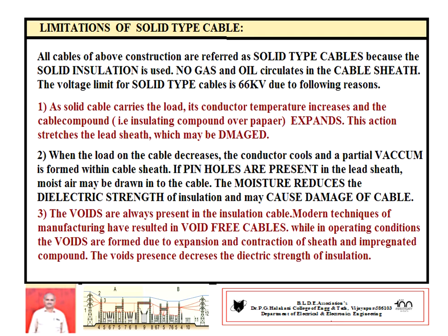Number 3, voids are also present. Voids may be present in the insulation of the cable, but modern techniques have been developed to prepare cables without voids. That is also an improvement in technology. But during operating conditions, these voids are also formed due to expansion and contraction of the sheath and the impregnated compound. This process of formation of voids decreases the dielectric strength.